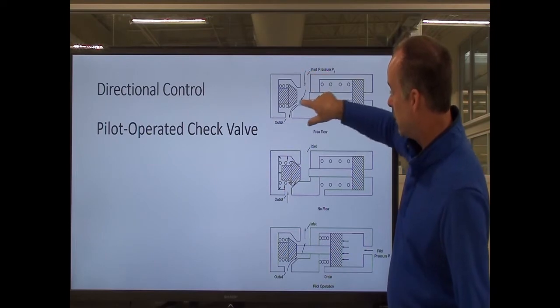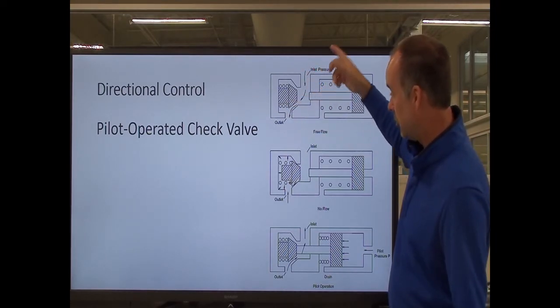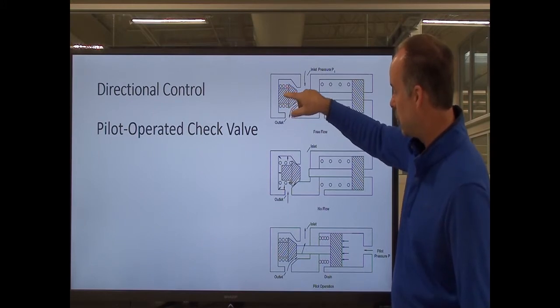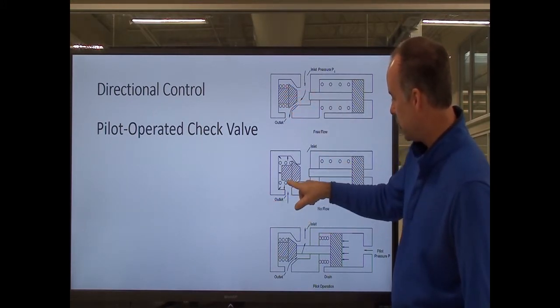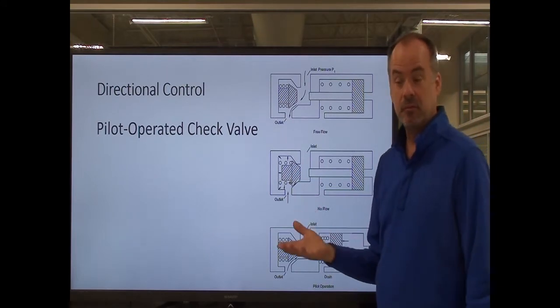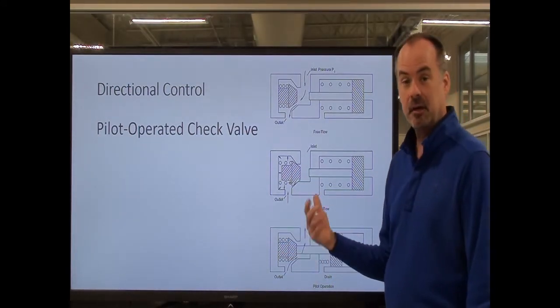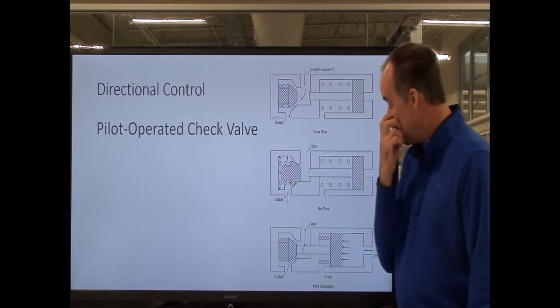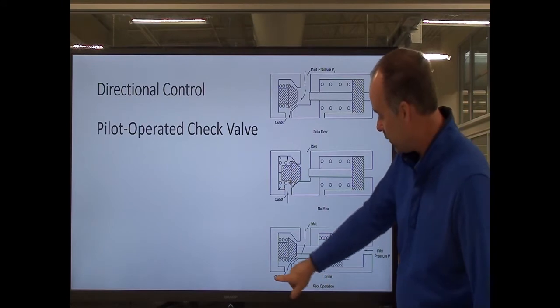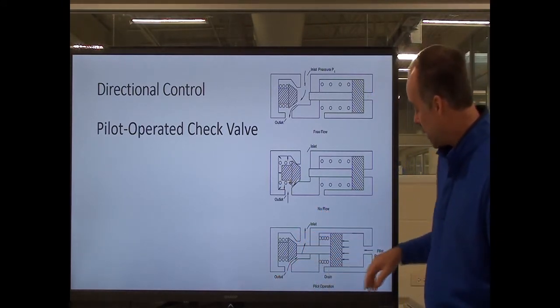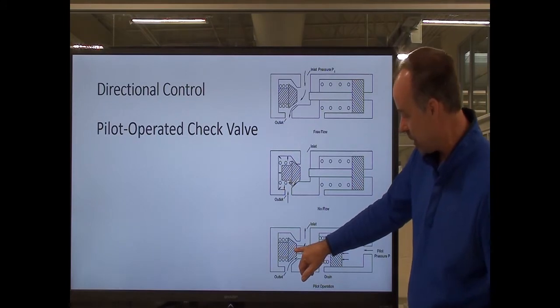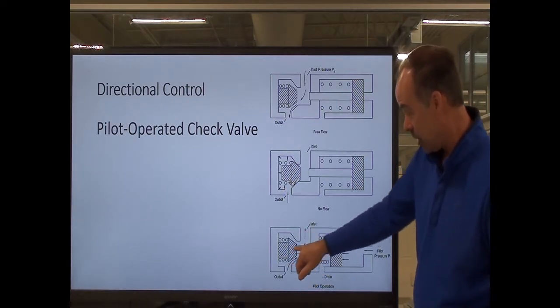On this type of valve, here's the check valve part. Under normal operation, the fluid comes in, pushes the poppet off its seat, and allows the fluid to flow against the spring. If I try to push the fluid back the other way, it'll actually push the poppet to the seat and block flow. But in some circuit applications I need fluid to flow backwards sometimes. So I've got pilot pressure on this check valve. If I've got fluid coming in and want to allow it to flow, I can put pressure on the pilot line, which actuates a piston that pushes down on the poppet seat and holds it open, allowing the fluid to flow.